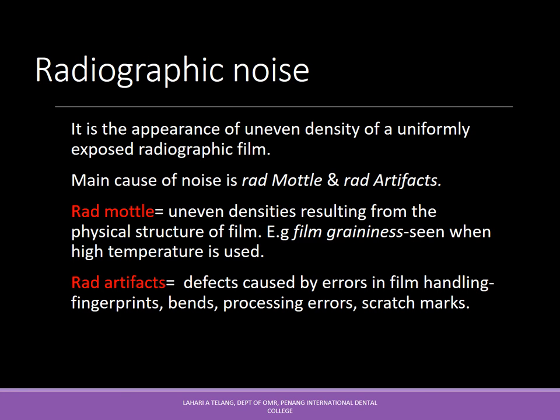Radiographic noise is the appearance of uneven densities on a uniformly exposed radiographic film. The main cause of noise is radiographic mottle or artifacts. Mottle refers to uneven densities resulting from the physical structure of the film, for example film graininess seen when high temperature is used. Artifacts are defects caused by errors in film handling like fingerprints, bends, processing errors, or scratch marks.